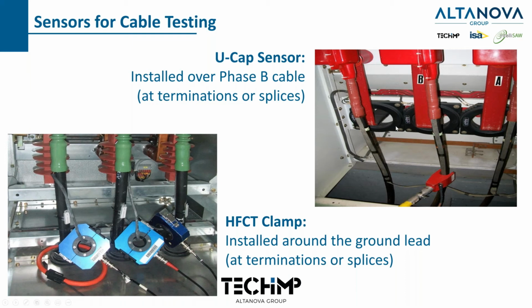Now, sometimes we cannot get around individual phases, because of the configuration, whether it's going into a switchgear and these are bundled together. We have large UCAP sensors which can go around all three phases, and we're able to pick up partial discharge with that sensor around all three phases.